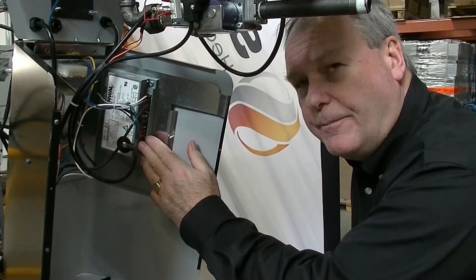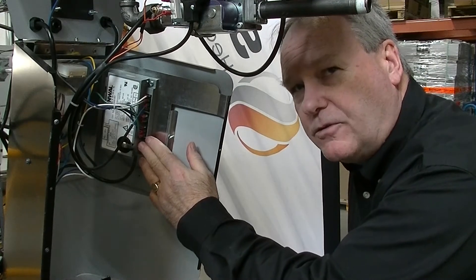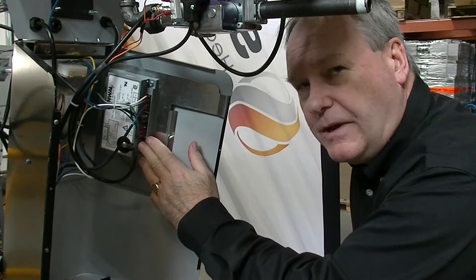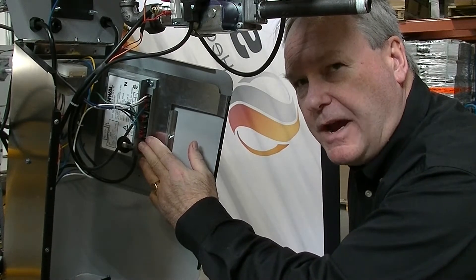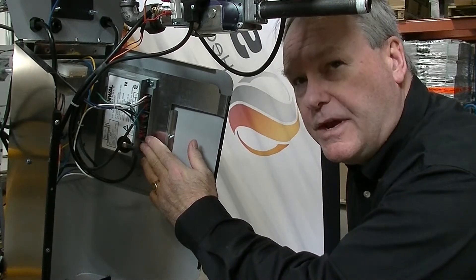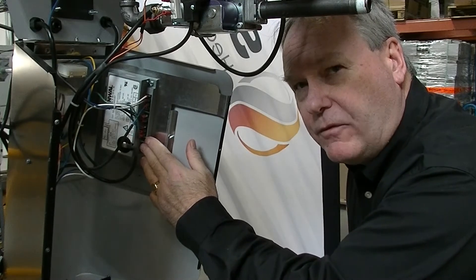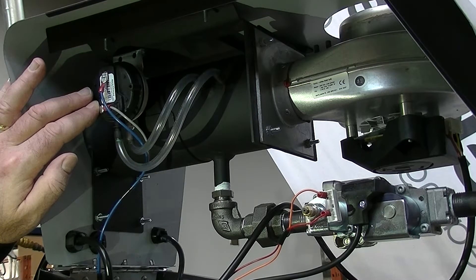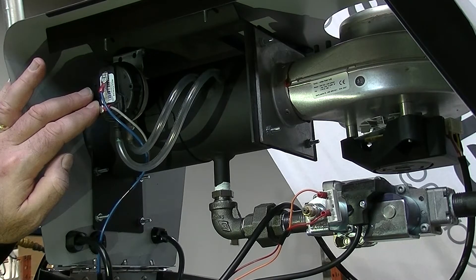Schwank has also kept the same reliable Fenwall controller on the new SuperTube burner design. This also allows you to continue to decide with a simple wiring choice whether you're going to run 120-volt thermostats or 24-volt thermostats. Another great improvement on the new SuperTube burner technology is Schwank has gone to a single pressure switch both for air proving and blocked flue. This is a single pressure switch for single stage, two stage, and modulating in the full series.